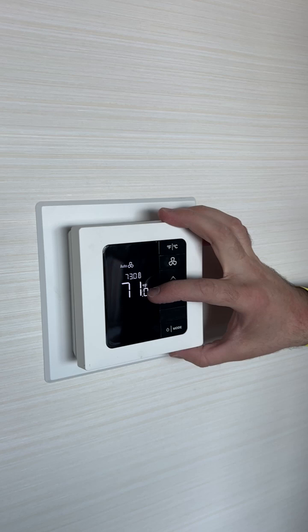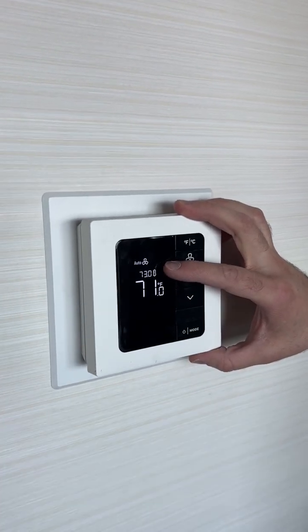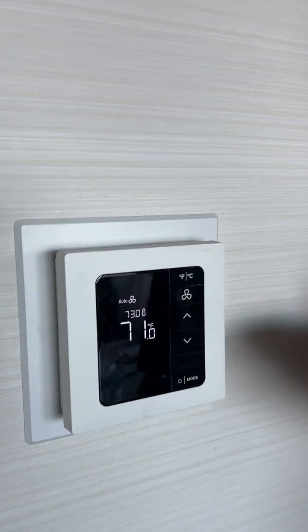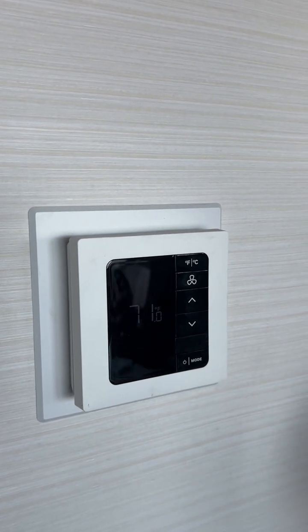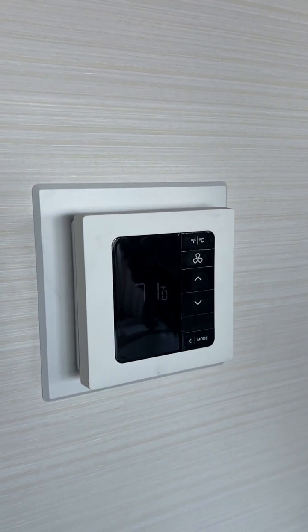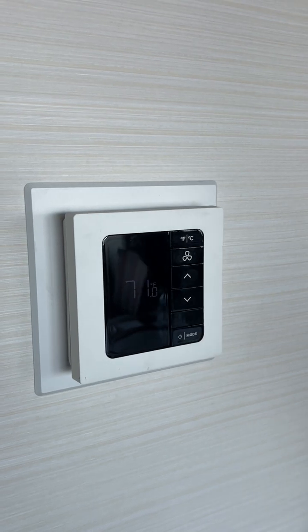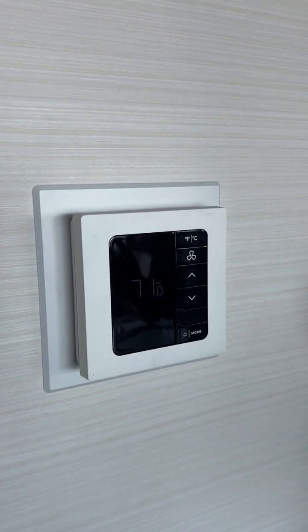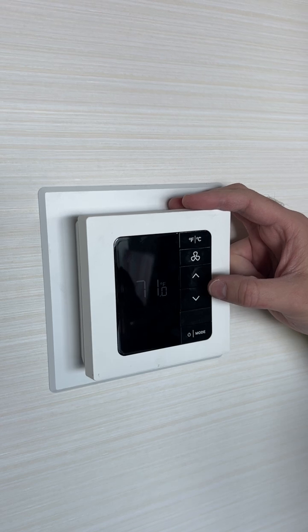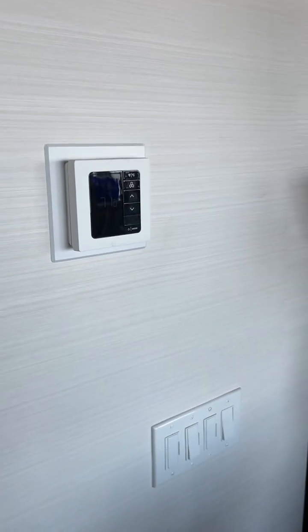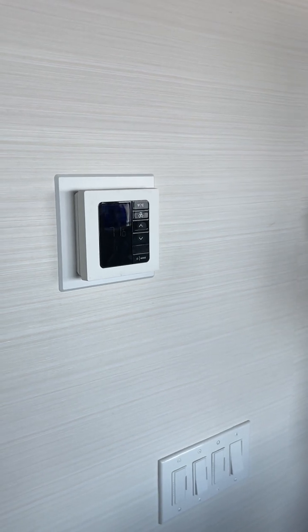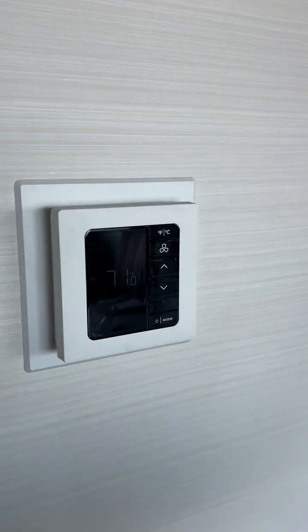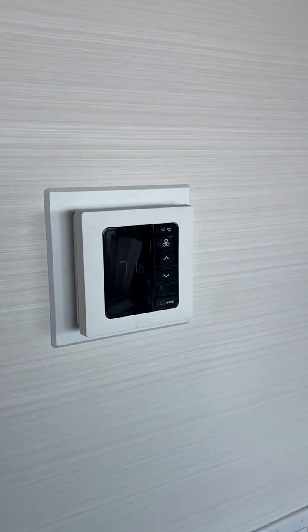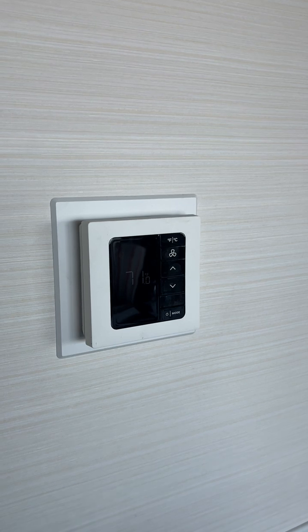So the big number is the set temp, the little number is the room temp. In this case, we're 2 degrees out, so it will be running, but it will probably be at low fan speed because it's very gradual. There's a 1 degree delta though, so once we get within 1 degree of the set temp, it won't try to keep cooling or keep heating, because we don't want to overcool or overheat the room and cause it to cool into a heat call or heat into a cool call.